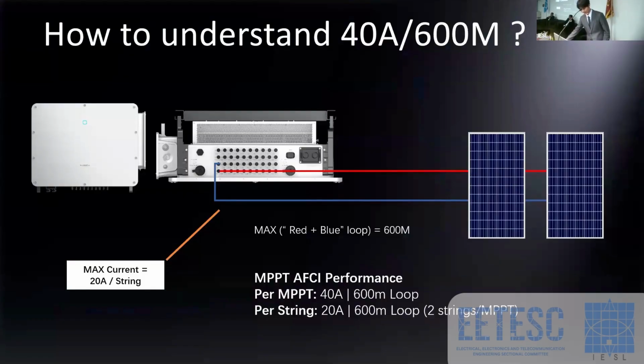Yeah, it's from the positive terminals of the inverter and it goes to the farthest PV panels and then goes back to the negative terminals. So for this loop, no more than 600 meters, AFCI will have a reliable performance. And for the 40 ampere, let me take an example from these products.